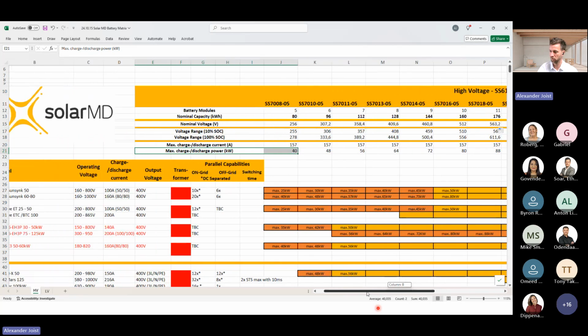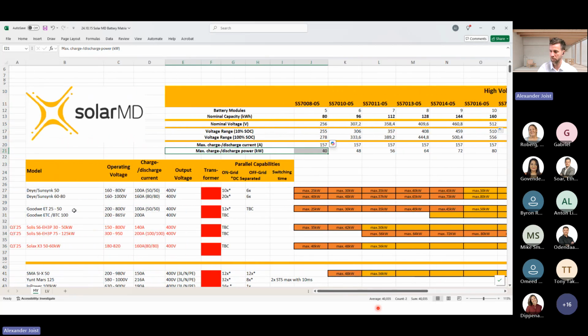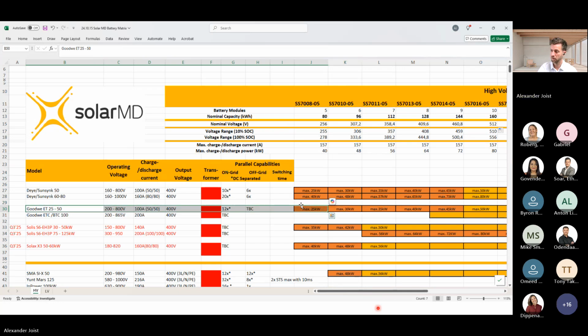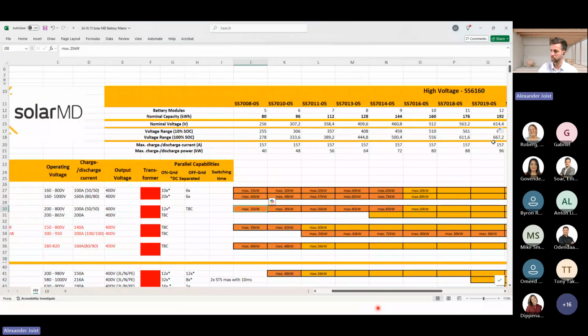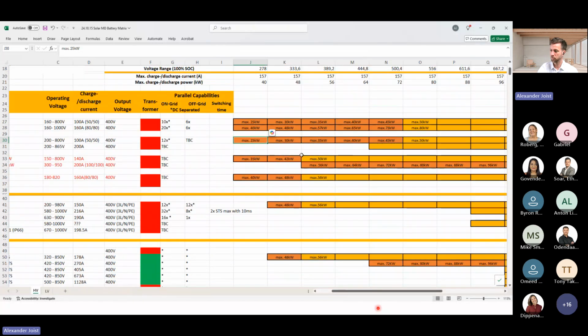But it still fits from the voltage to any of these inverters, even though they might be bigger. It's quite important that this battery has an output power of 40 kilowatt maximum, but on the GoodWe 50 or 25, we can do a maximum of 25 kilowatts. And what is the reason for that? Because we only have a charge and discharge current of 100 amp. So the 256 volt multiplied by 100 amps is only 25 kilowatt. And this is what you can see in the compatibility matrix that we have drawn up.